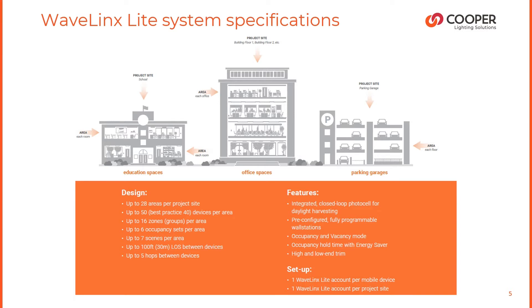An area is considered to be a network — devices working together via mesh communications to accomplish a common goal. You may have up to 16 zones of control groups in an area, up to six occupancy sets per area, and up to seven custom defined scenes per area. WaveLinx Lite is a wireless system, and devices need to communicate with each other, so we specify up to 100 feet or 30 meters line of sight between devices. The more devices a particular device can communicate with, the more robust and reliable the communication, and the shorter the latency — everything responds together more quickly.